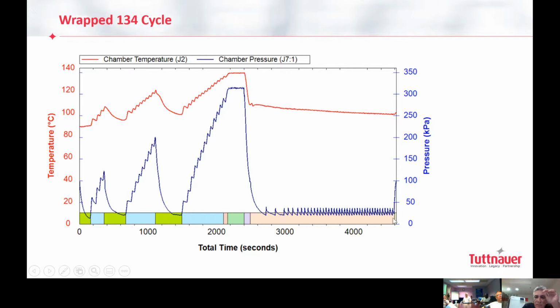So we are creating this vacuum, and the pulses you see here are a concept that can be configured, depending on the load. We will speak about it at the end, if we have time and if you are interested, to define or configure the right cycle or the right program for the right load or customer. And at the end, we are filling the air back into the chamber in order to break the vacuum.